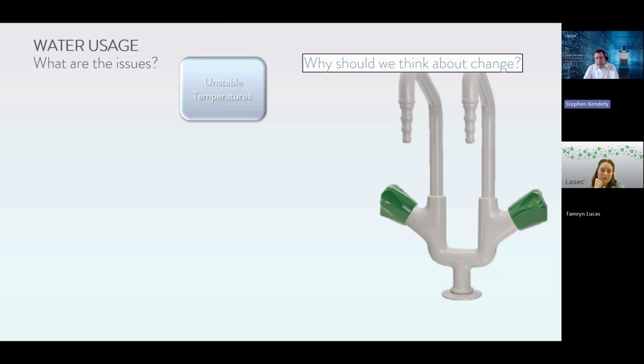I've come across cases in the past where, for example, a university had its water tank on the roof in a big black box. And during the summer, the temperature of that water may get up to somewhere around 30, 35, 40 degrees centigrade. It was on the roof to be able to provide a head of pressure. And the university spoke with us regarding the temperature control, because at 40 degrees, the chemistry lab wasn't getting any cooling, and they needed to improve the cooling because there was a health and safety issue with not trapping the solvents that were escaping from reaction vessels.